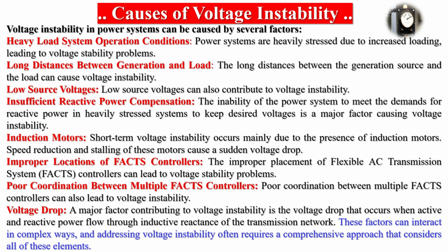Induction motors. Short-term voltage instability occurs mainly due to the presence of induction motors. Speed reduction and stalling of these motors cause a sudden voltage drop. Improper locations of FACTS controllers. The improper placement of flexible AC transmission system FACTS controllers can lead to voltage stability problems. Poor coordination between multiple FACTS controllers. Poor coordination between multiple FACTS controllers can also lead to voltage instability. Voltage drop. A major factor contributing to voltage instability is the voltage drop that occurs when active and reactive power flow through inductive reactance of the transmission network.